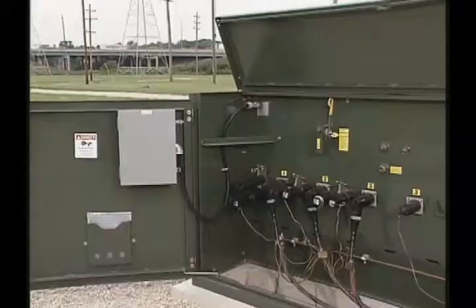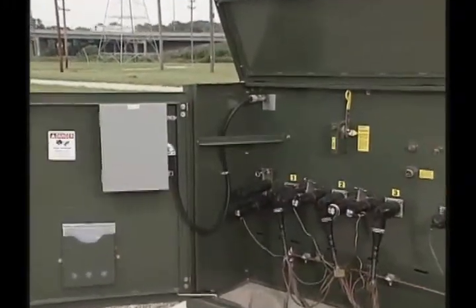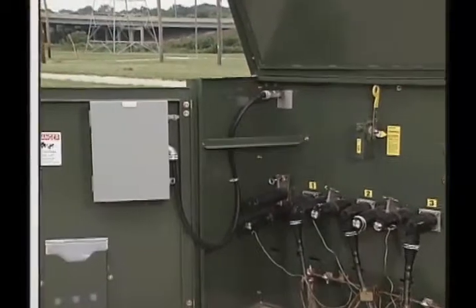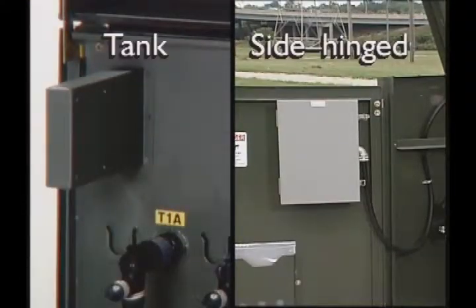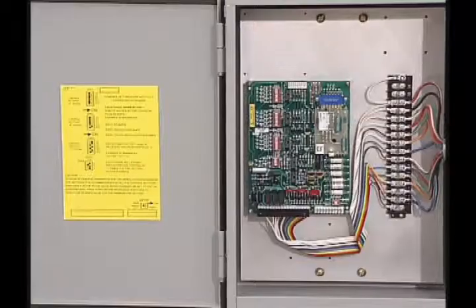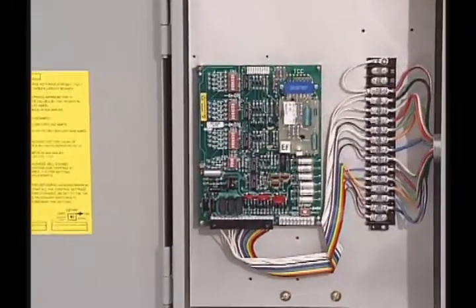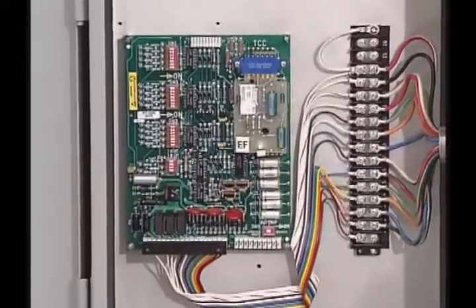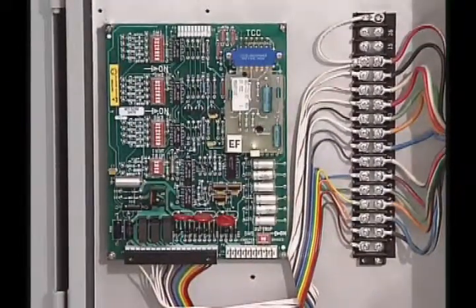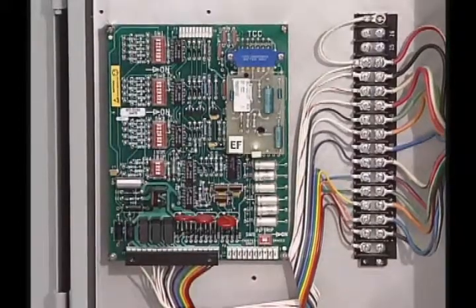The Kyle tri-phase control provides the operating intelligence for the VFI. The tri-phase control can be mounted on a side hinge door or the tank of the VFI unit, depending on the application. The tri-phase electronic control is a solid-state circuit board with a plug-in time current curve, or TCC, module.